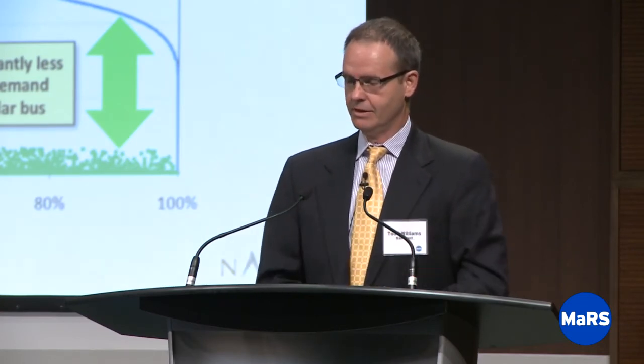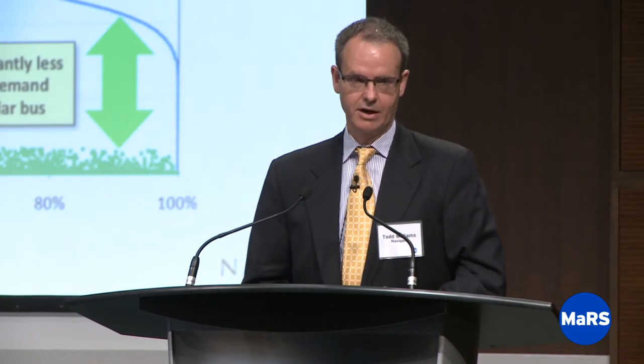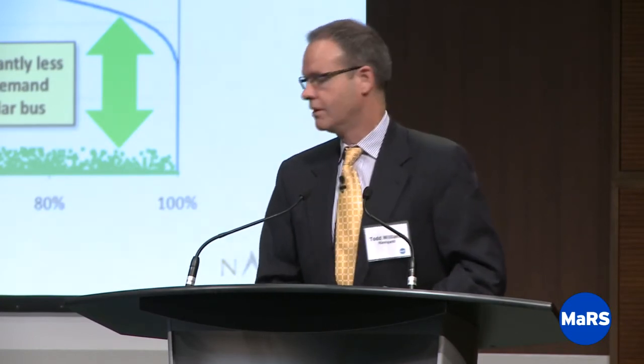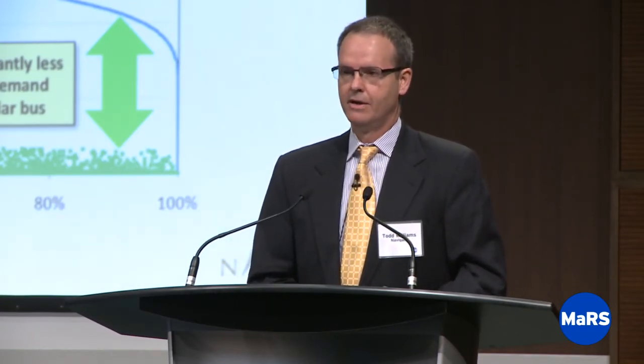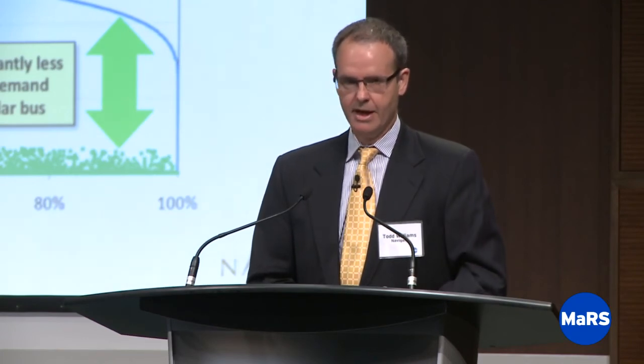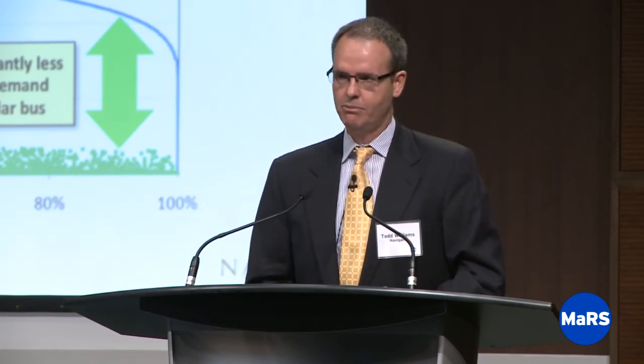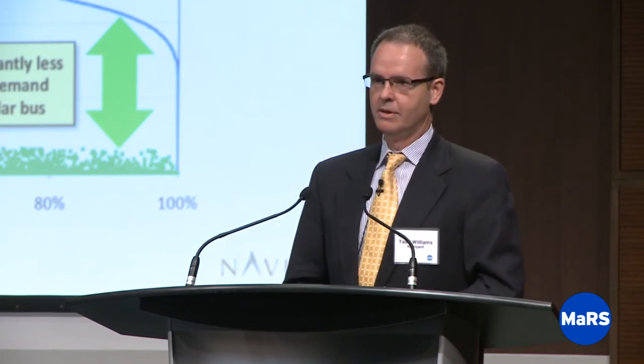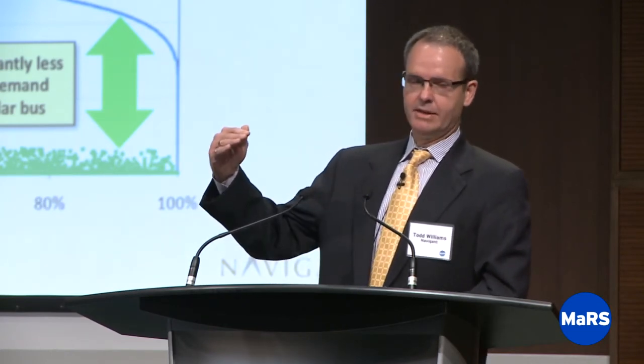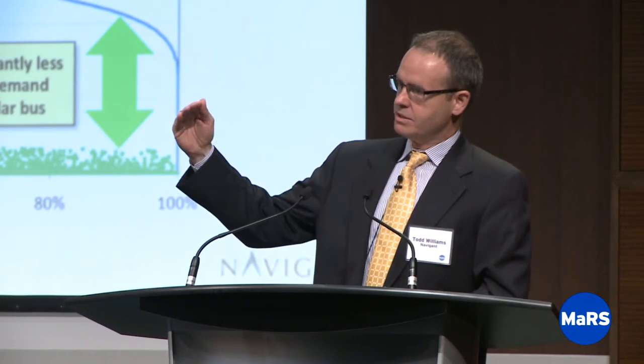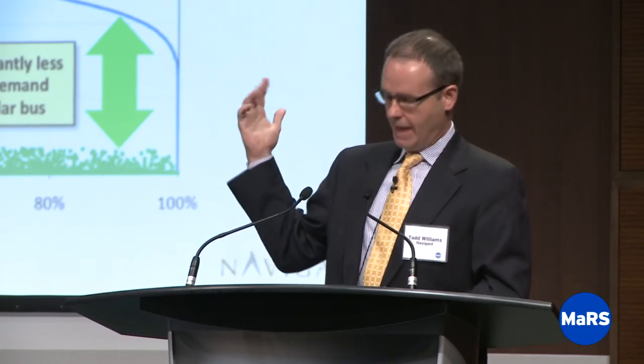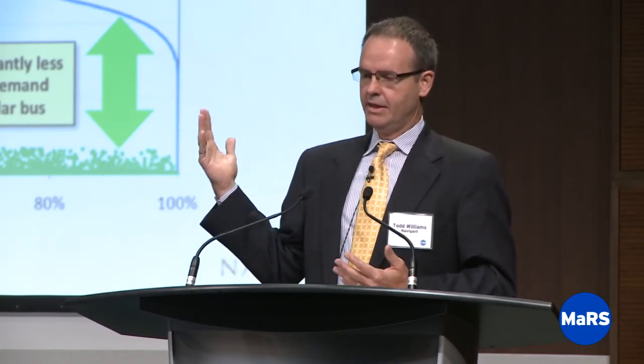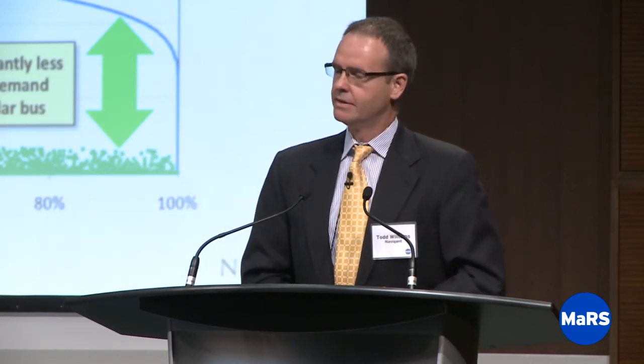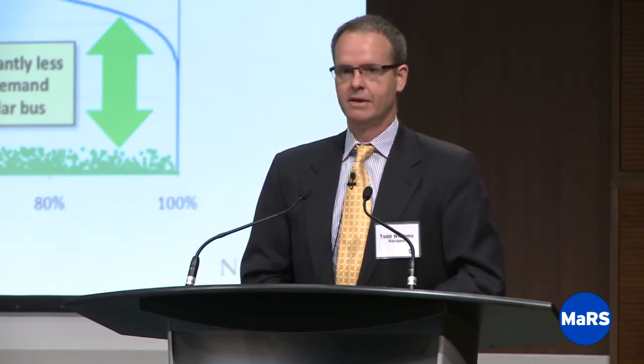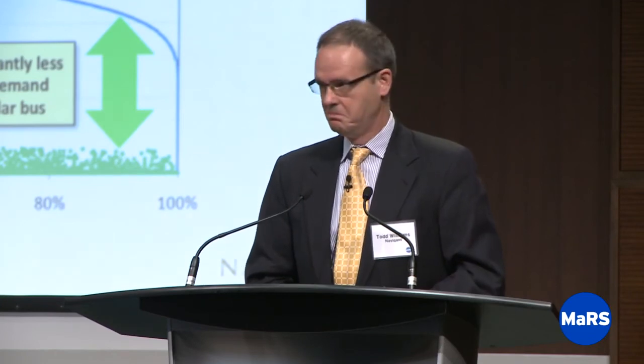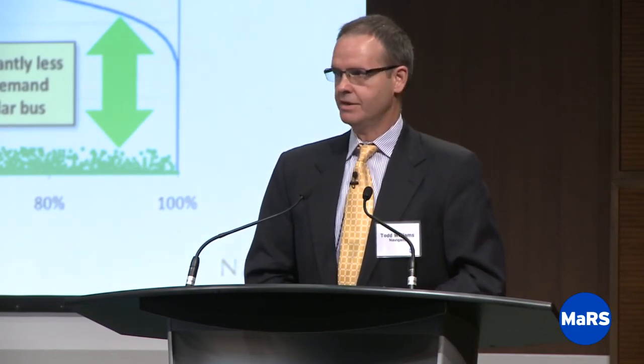So there's 8,760 green spots there. Many of them are zero because at night there's no output. What's interesting to look at here is that limit, 7% of maximum output: there's an awful lot of headroom between the maximum that the PV would be and the lowest level. On this particular chart, I don't see any point at which the PV output is exceeding the loading. So it's definitely a safe limit. Is it conservative? Probably, but it's certainly safe.